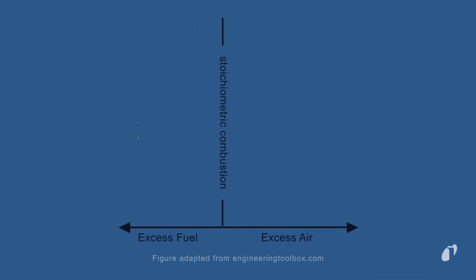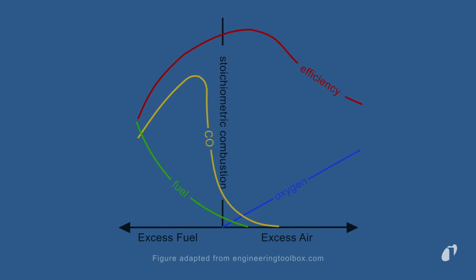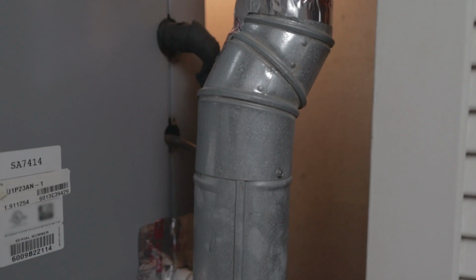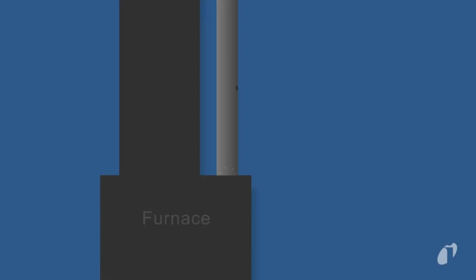The air-to-fuel ratio is key to achieving complete combustion. Understand the stoichiometric combustion curve to optimize the heating system's efficiency. Introducing too much air or fuel will result in incomplete combustion, reducing the efficiency. Locate the test port on the flue pipe. If there is no test port, carefully drill a 1/4-inch hole. Keep in mind that dropping debris into the fan can damage it. Follow the manufacturer's instructions for the recommended location. A test port too low or too high may result in inaccurate readings or damage to the analyzer.